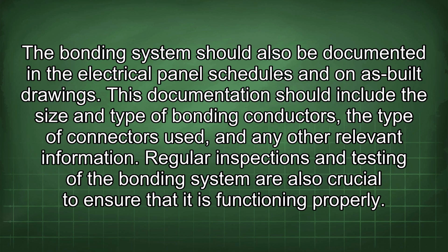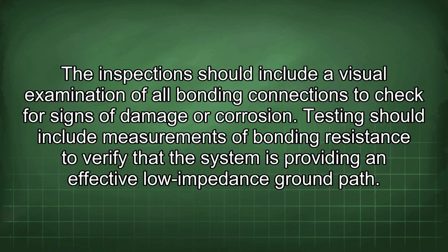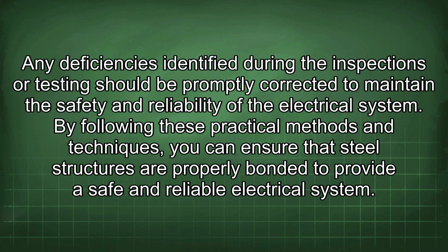Regular inspections and testing of the bonding system are also crucial to ensure that it is functioning properly. The inspection should include a visual examination of all bonding connections to check for signs of damage or corrosion. Testing should include measurements of bonding resistance to verify that the system is providing an effective low-impedance ground path. Any deficiencies identified during the inspections or testing should be promptly corrected to maintain the safety and reliability of the electrical system.